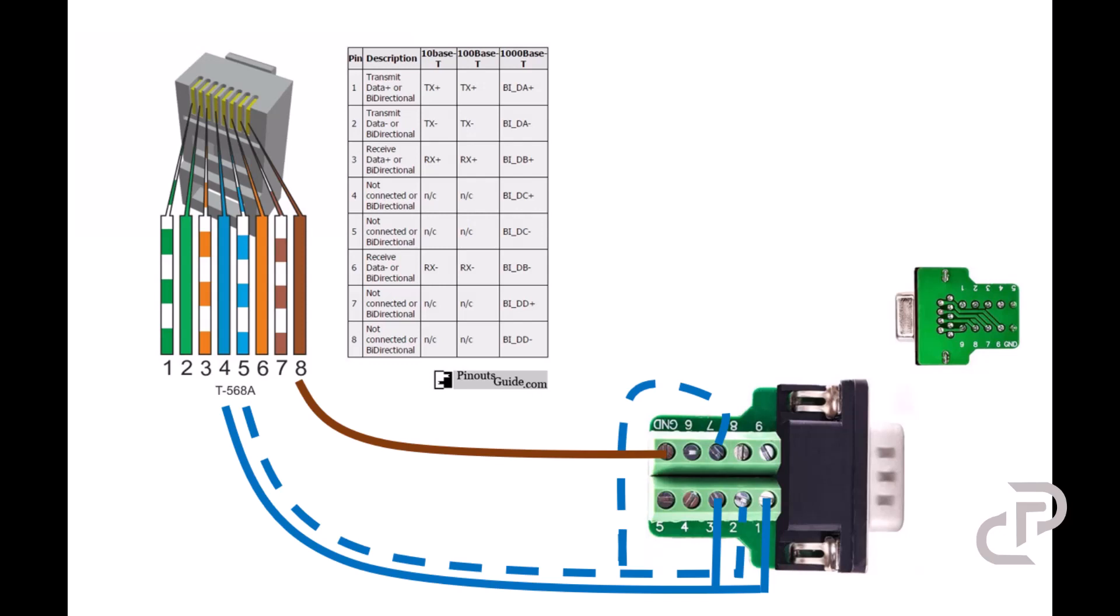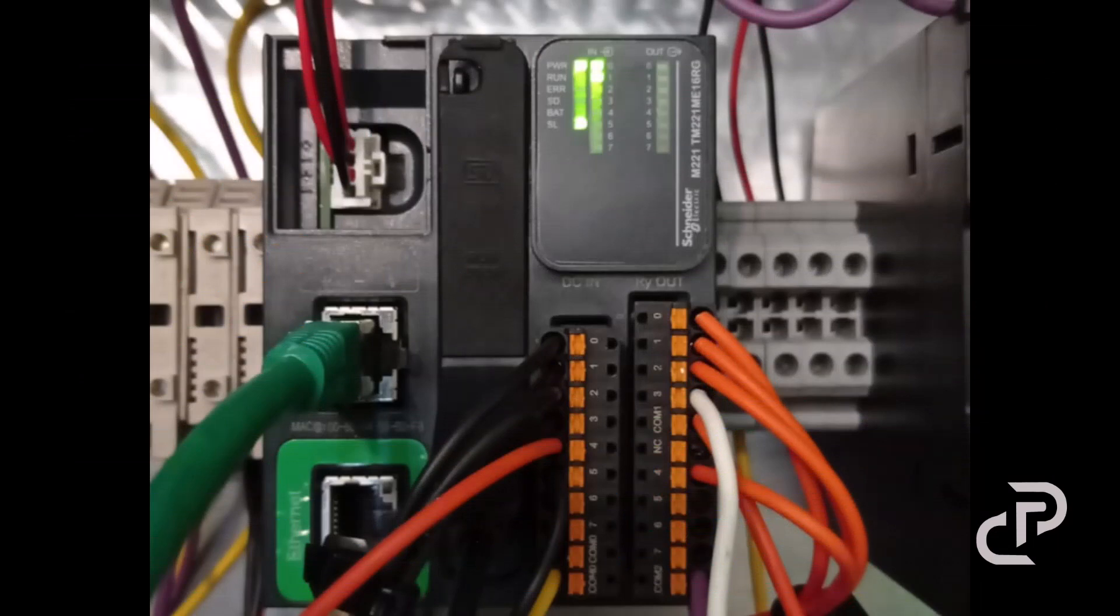You have to do these jumpers, otherwise the HMI has frame error or parity error, and it will not connect to PLC. Here in this picture you can see the real implementation.